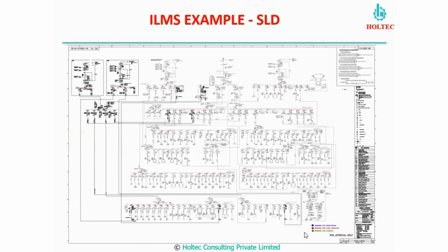We define the area, the equipment or the tie breakers or the source system, where we can have either power monitoring, or load shedding to initiate; we can identify the areas where we can have certain controls. Controls means controls basically on power factor, bus capacitors, controls on certain tie feeders to change the mode of operation if the situation demands. So there can be a bus coupler, there can be a tie feeder which can be controlled through this ILMS system.